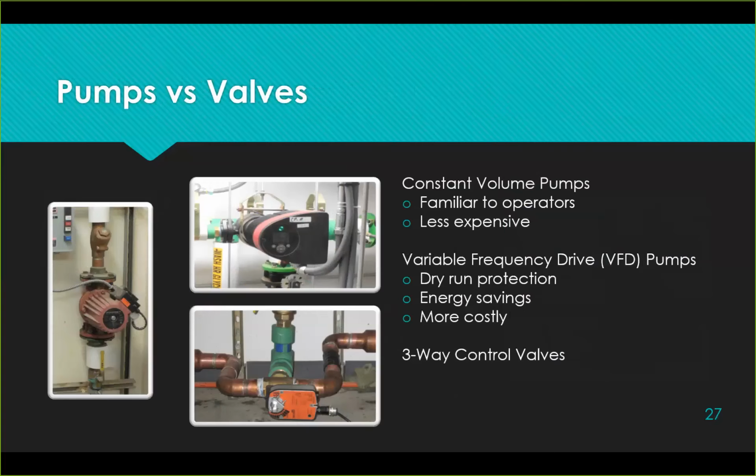Variable frequency drive pumps allow us, in many instances, dry run protection built in, so we can avoid flow switches and pressure switches in the system and potential false alarms. They provide an energy savings. They may be a little more costly up front, but they can also be beneficial. And then alternately, there's always control valves. So you can use three-way control valves to tie the heating into your existing system.